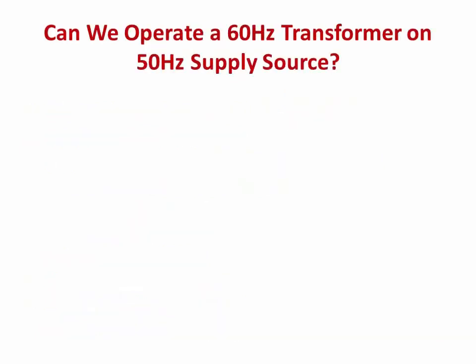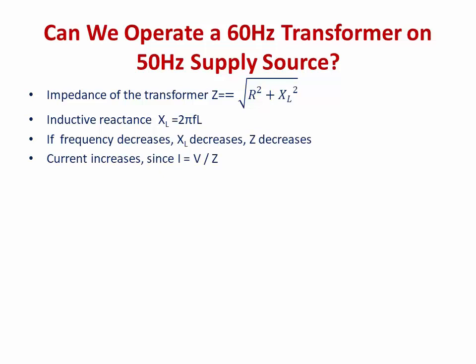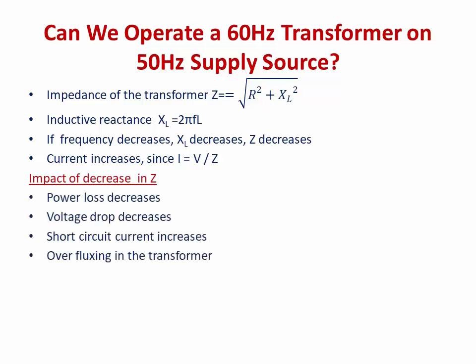Another question: can we operate a 60 Hz transformer on a 50 Hz supply? Using the same formula — Z depends on R and XL, and XL = 2πfL — if the frequency decreases, inductive reactance decreases, which decreases impedance, thereby causing an increment in current. Will this increment in current or decrease in impedance have an impact on the transformer? Let us discuss that.